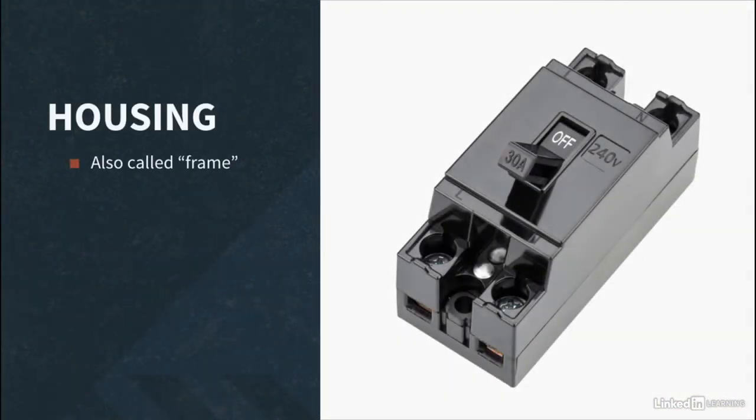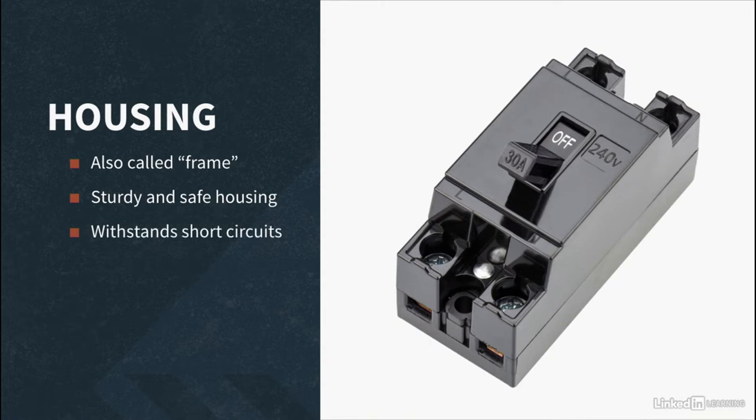The frame. Circuit breakers' physical housing or frame, as it's most commonly referred to, must provide the integrity needed to properly withstand the interruption process and achieve the desired interrupting. Occasionally, the interruption process has a great deal of electrical force and energy, like during a short circuit. Therefore, the circuit breaker is built to withhold these very high energy incidents.